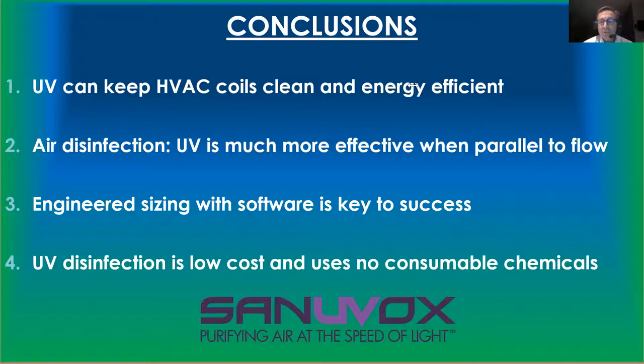If it's too cold, then you don't have enough mercury vapor, and your number of UV emitters goes down. So that's why there's a peak. The ideal operating temperature is about 40 Celsius for a lamp. Anything hotter or cooler, you'll see a reduction. Another question from Andrew McLean.